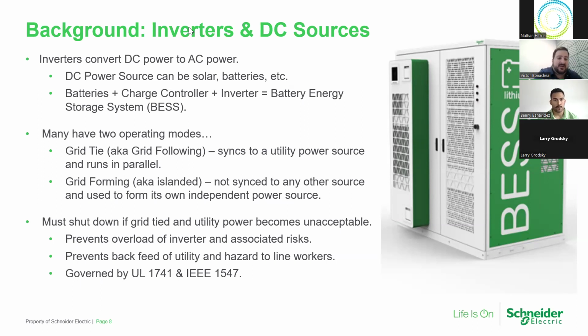Now, the interesting thing is a lot of inverters out there on the market, not all of them, but many of them that you'll see in these applications, have two operating modes. There's grid tie mode, which goes by a couple of different names. Some people call it grid following, or grid interactive. That means the inverter is synchronizing its power output to another AC power source and providing power out in parallel with it.